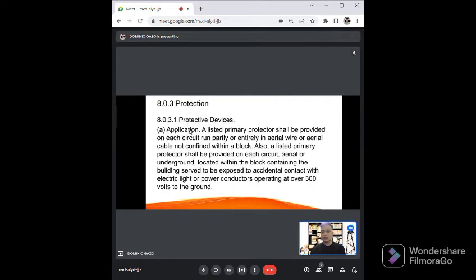For protective devices, for application, a listed primary protector shall be provided on each circuit run partly or entirely as aerial wire or aerial cable not confined within the block. And it shall be protected on circuit, aerial or underground, by locating within the block containing a building served to be exposed to accidental contact with electric light and power conductors operating over 300 volts to ground.